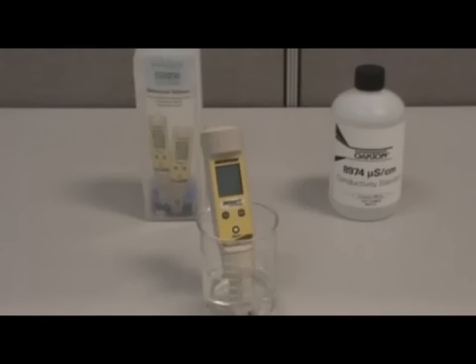Choose the TDS value off the label on your standard according to the type of samples you will be measuring. To ensure an accurate and stable calibration, you should condition your tester in water or alcohol for 30 minutes prior to calibration.